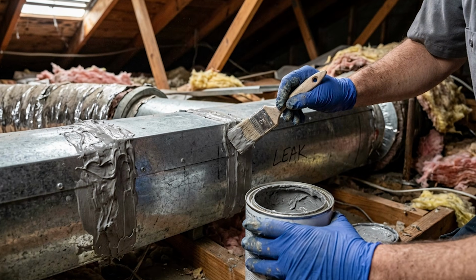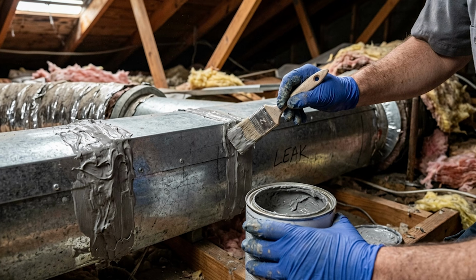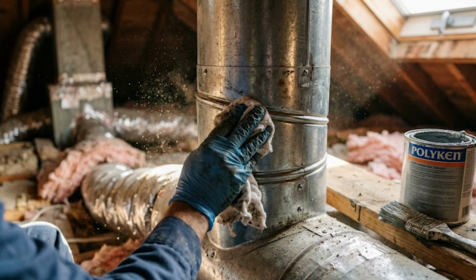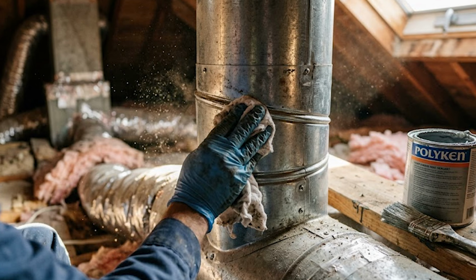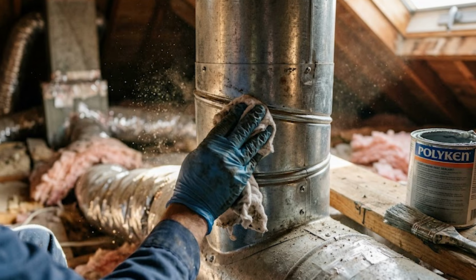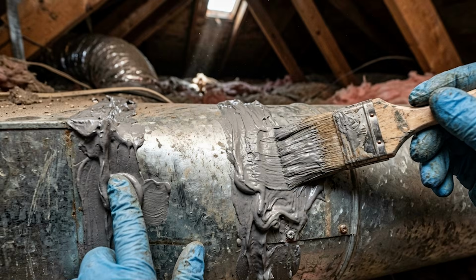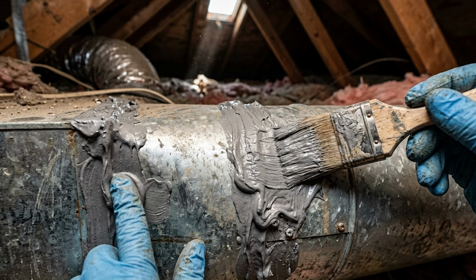Mastic is easy to wash off when it is wet, but becomes quite sticky as it dries. Wipe the duct surface with a dry rag to remove dust and debris. Adhesion on a dirty surface is significantly weaker. Apply the mastic with a cheap paintbrush or with a gloved finger.